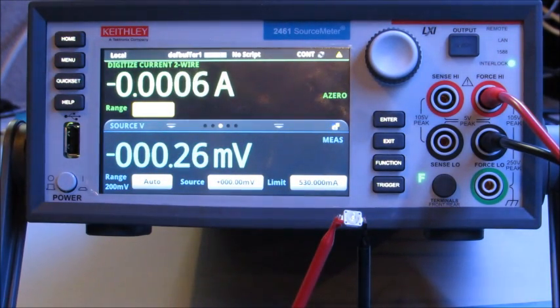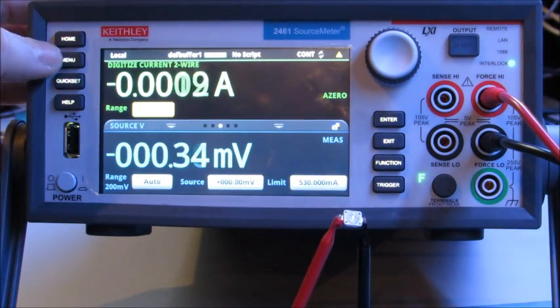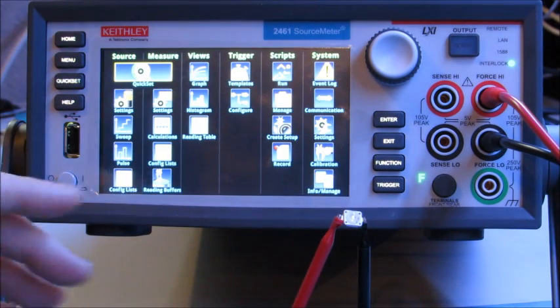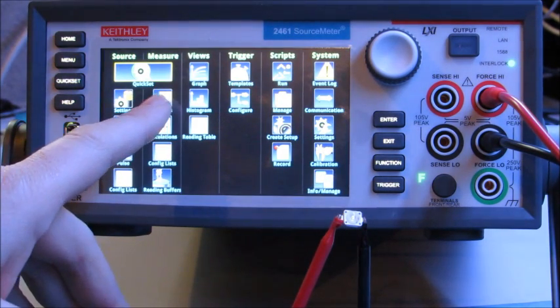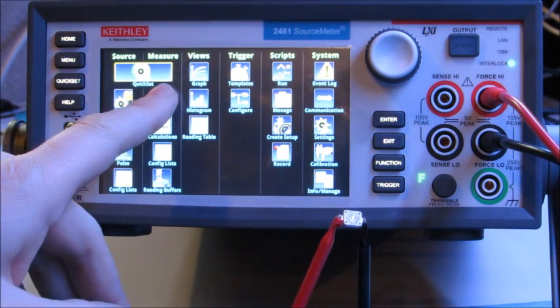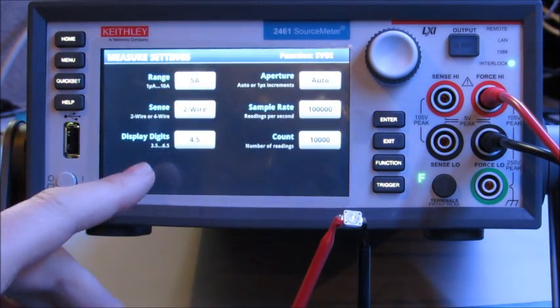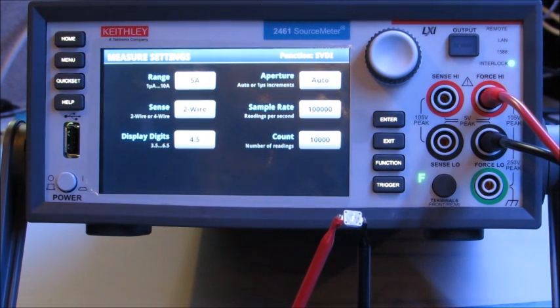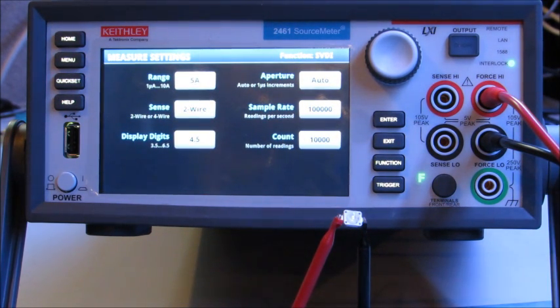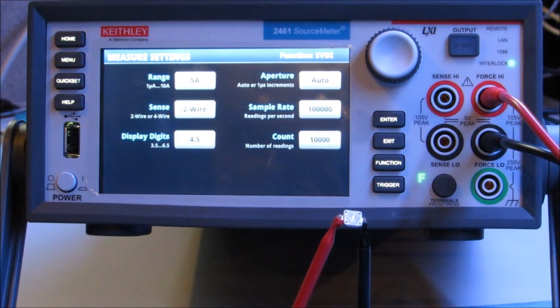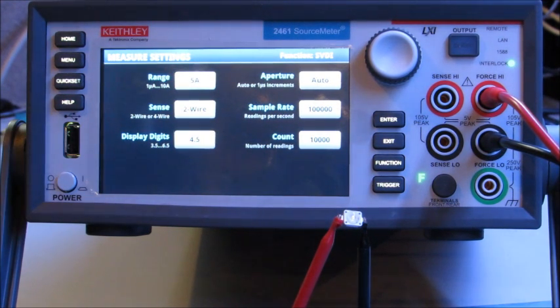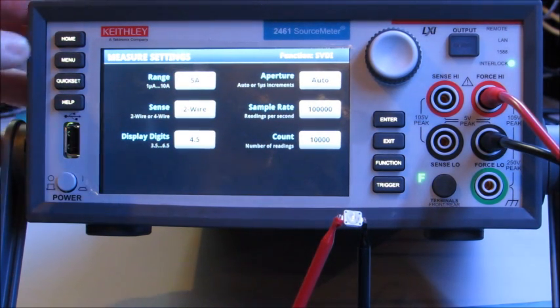Now I hit my menu button and I can go to my measure settings icon here. And right now the sample rate is set to 100,000 readings per second and a count of 10,000 readings. So I'm going to leave it there for right now.